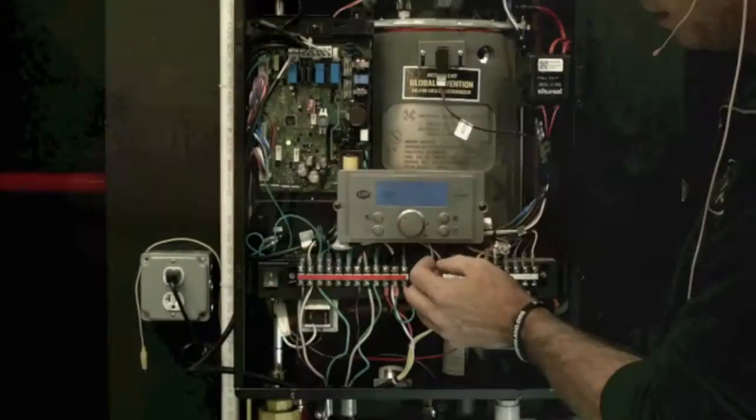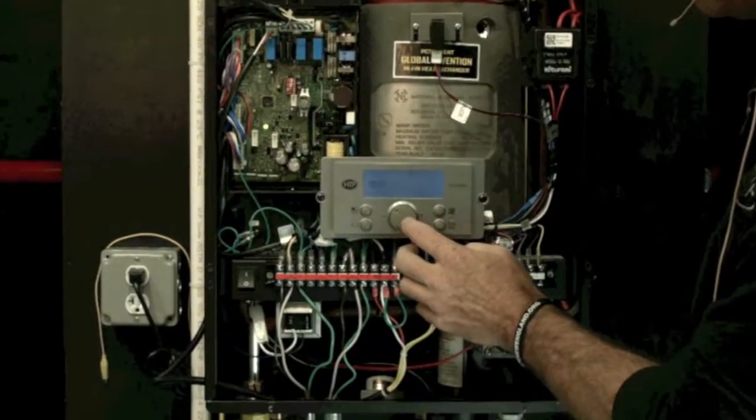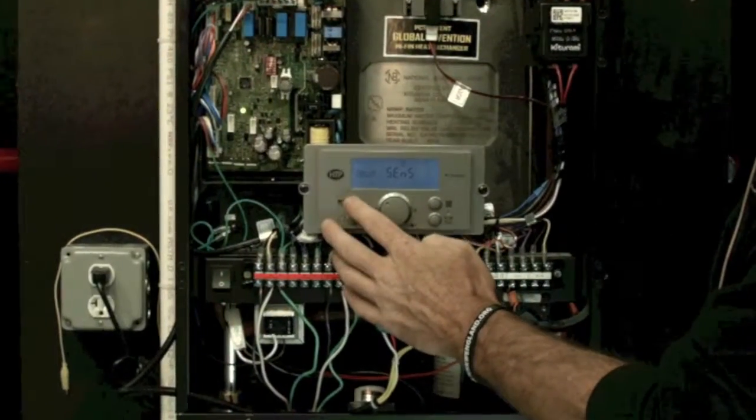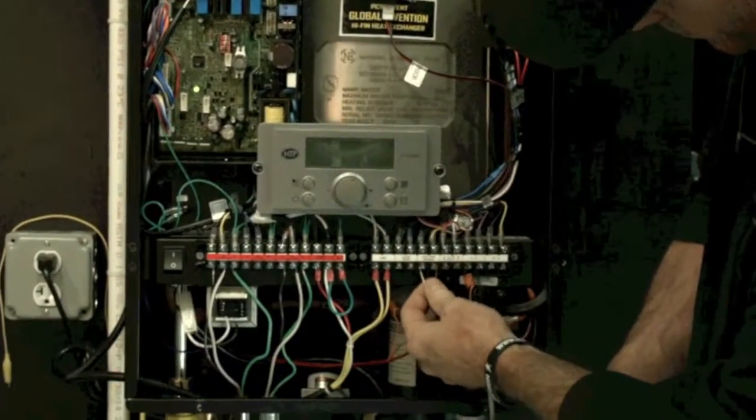If sensor is selected in installer parameter 39, then ensure proper wiring connections to the low voltage terminal strip. If wiring is correct, then resistance must be verified using an appropriate meter.